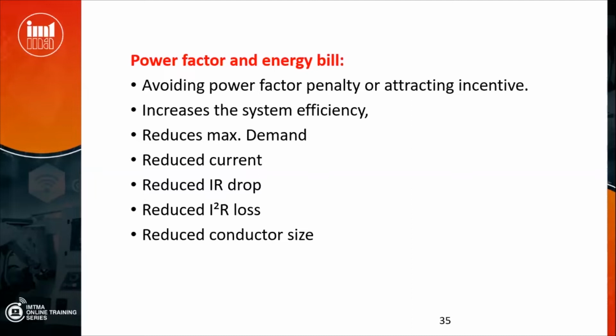Reduced current means reduced IR, that is I into R, resistance into current. It also reduces I squared R, which is the heat loss. Whenever current flows through a conductor, current squared into the resistance of the conductor is the heat generated, and for that heat you are spending some energy. When I say IR drop from the sending end to the receiving end, when a current I is flowing, I into R is the resistance of the wire, so much drop will be there.